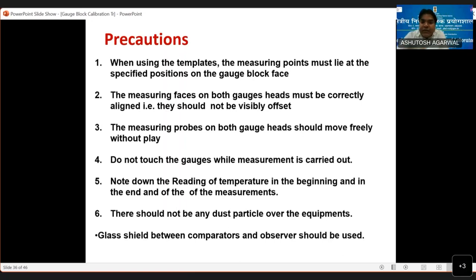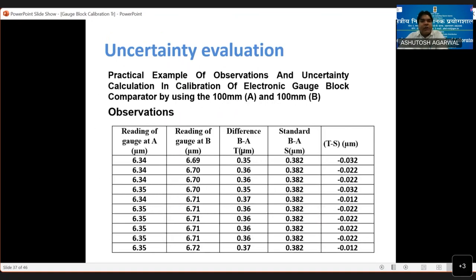Note down the reading of temperature in the beginning and in the end, and check during measurement whether there is any change in temperature. So 0.1 degree brings a lot of change: alpha L delta T. There should not be any dust particle. A glass shield, as I told, between the comparator and the observer should be used. So now I hope you understand how to calibrate the gauge block. Then we come to the uncertainty part.